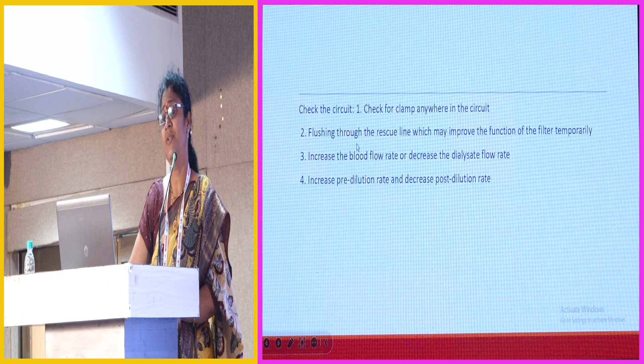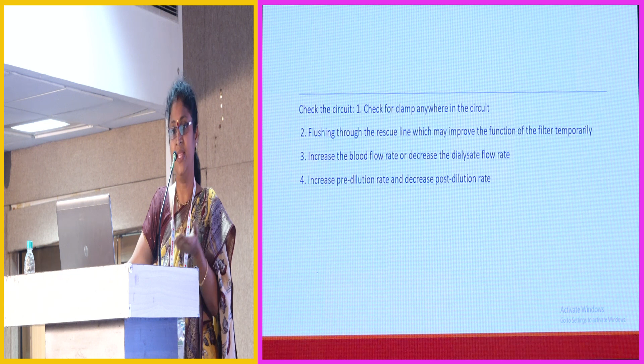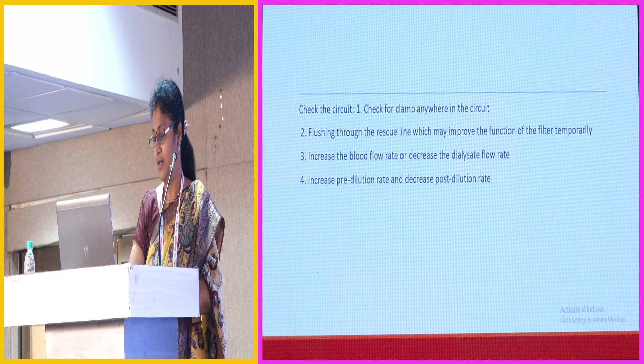So check for the clamp. The one thing that we can do whenever we see clogging of the filter is, through the rescue line, we can try to flush the filter and see. This morning we have seen that fouling can be external and internal clogging. If we have realized it is external clogging, flushing would help. Suppose it is internal fouling, then nothing would help and we need to change the filter. Increase the blood flow rate and decrease the dialysate flow rate. So these are all, I tried to summarize about the pressures and pressure alarms.